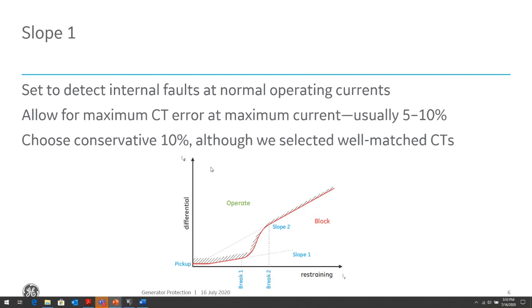A good value is 10%, and again, based on system studies and conditions we've seen in the field, about 10% is a good compromise. If you have DC offset that can cause your CT to go into some level of CT saturation, then maybe 30%, 40%, even 50%. Some people actually set slope 1 and slope 2 to the same setting because their CT selection is god awful, and it's a really badly performing CT, and they might need to set the 2 slopes the same.